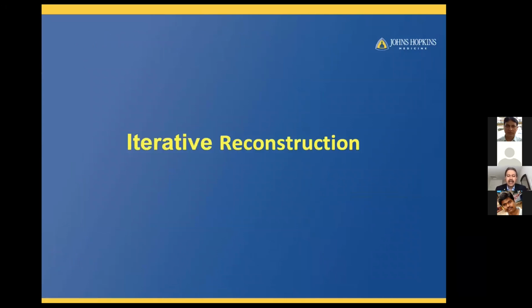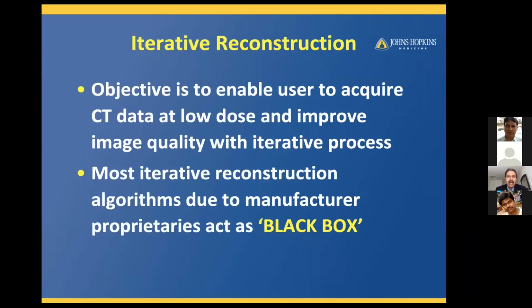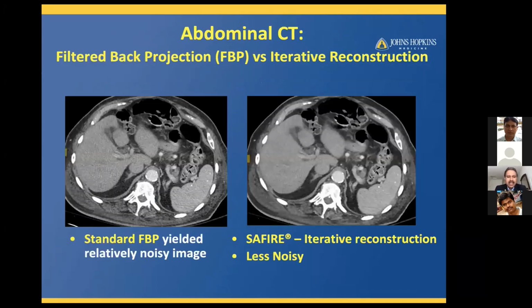Iterative reconstruction has helped a lot, because the objective is to enable the user to acquire data at a low dose and improve image quality with the iterative process. Most iterative reconstruction algorithms are manufacturer proprietary, known as a black box. What's shown here is the standard reconstruction method on an abdominal image. The same thing done with iterative reconstruction can decrease the noise to some extent. That's why iterative reconstructions are used: you can acquire the image at a lower dose, where the image is quite noisier, and increase the image quality by using iterative reconstruction.